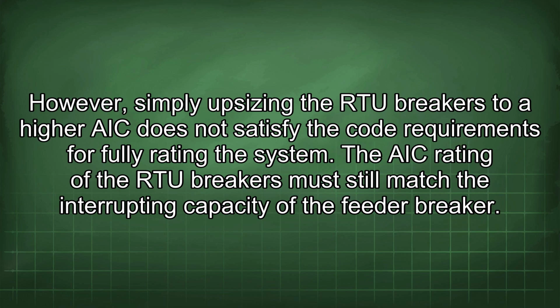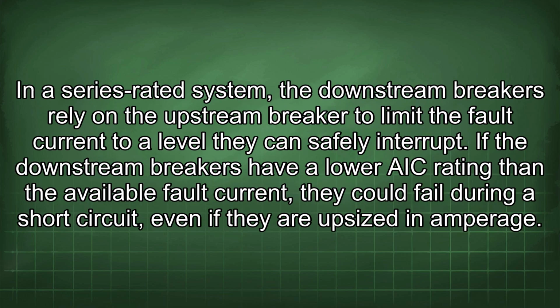However, simply upsizing the RTU breakers to a higher AIC does not satisfy the code requirements for fully rating the system. The AIC rating of the RTU breakers must still match the interrupting capacity of the feeder breaker. In a series-rated system, the downstream breakers rely on the upstream breaker to limit the fault current to a level they can safely interrupt. If the downstream breakers have a lower AIC rating than the available fault current, they could fail during a short circuit, even if they are upsized in amperage.